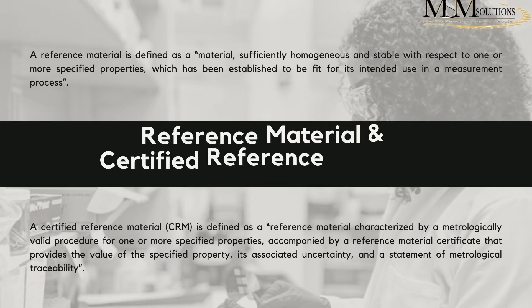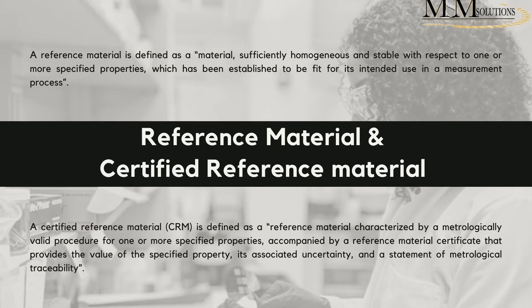First let's recap on the definitions of a reference material relative to a certified reference material. A reference material is defined as a material sufficiently homogeneous and stable with respect to one or more specified properties, which has been established to be fit for its intended use in the measurement process. A certified reference material, a CRM, is defined as a reference material characterized by a metrologically valid procedure for one or more specified properties, accompanied by a reference material certificate that provides the value of the specified property, its associated uncertainty, and a statement of metrological traceability.